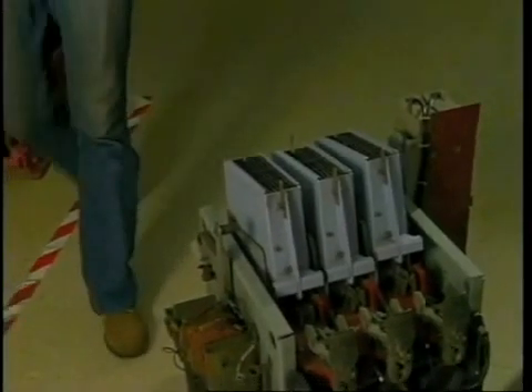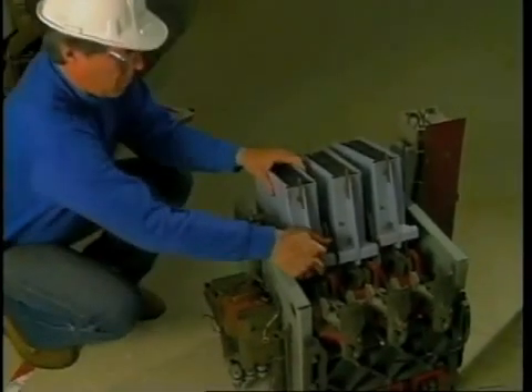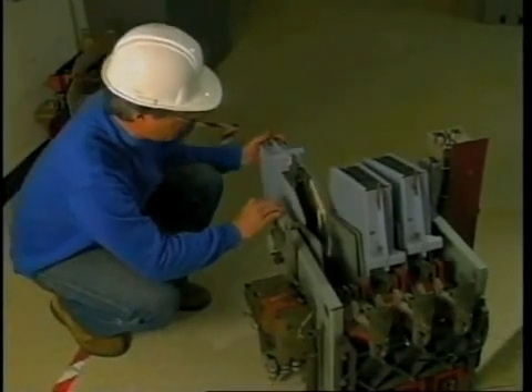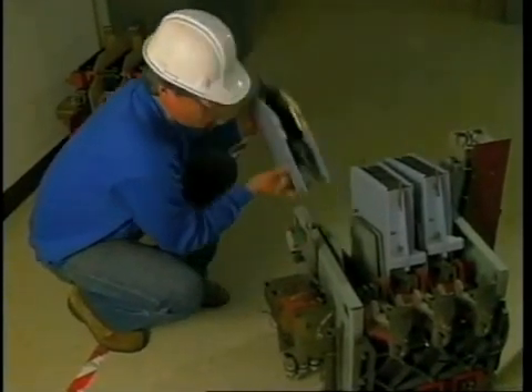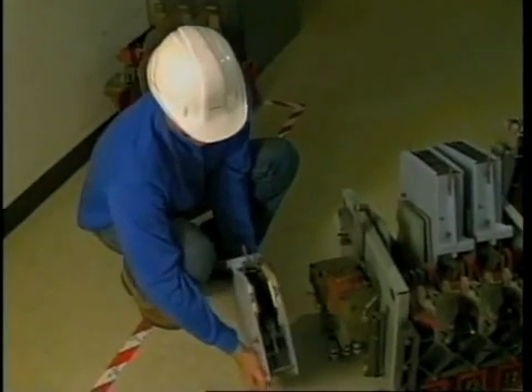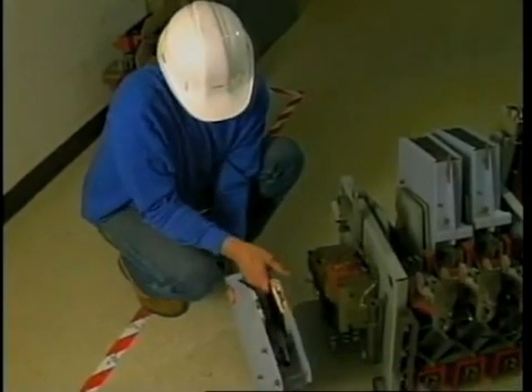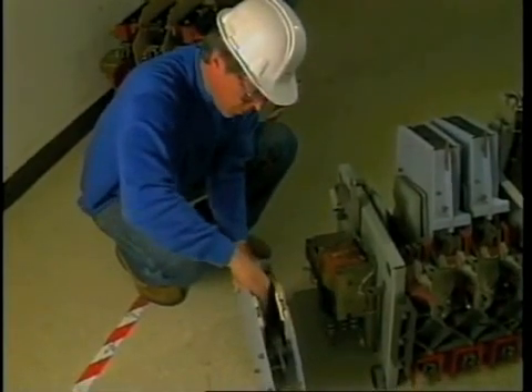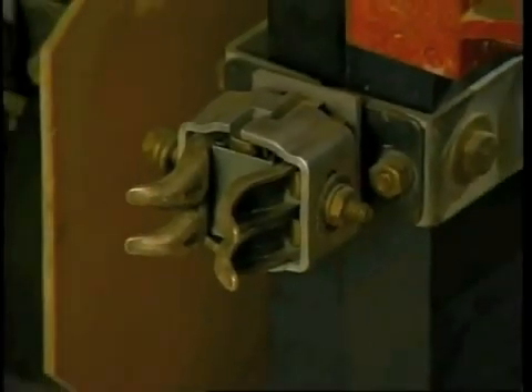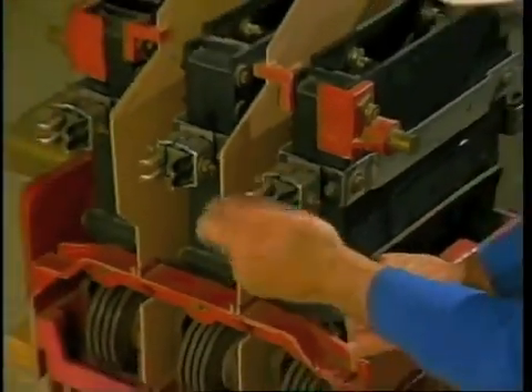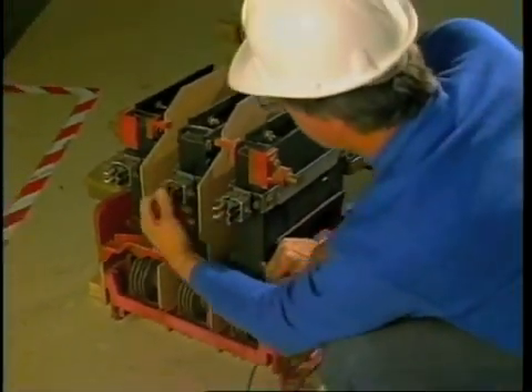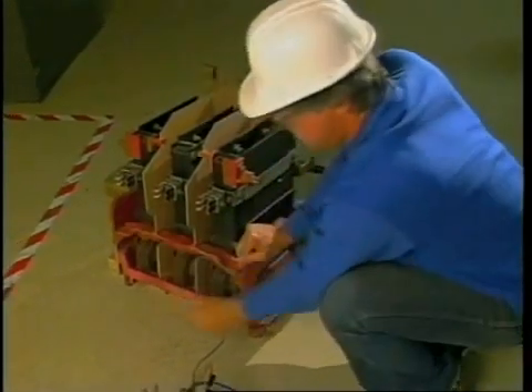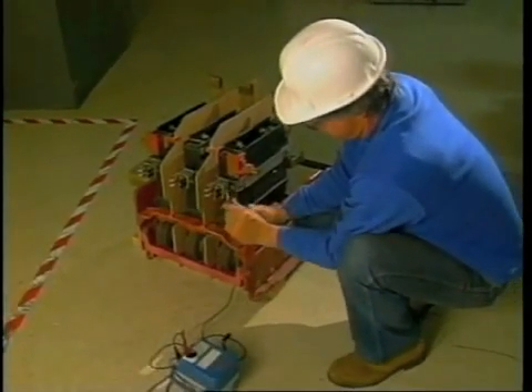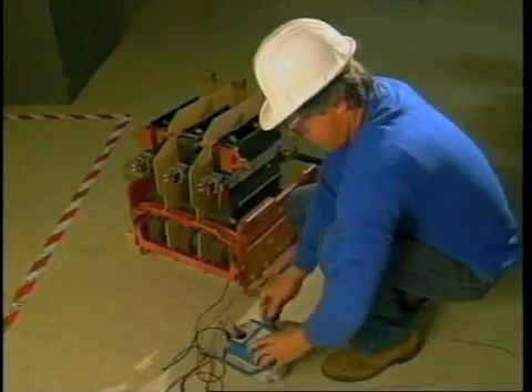All contactors have arc chutes that interrupt arcs during fault conditions. The arc chutes on contactors are smaller than those found on circuit breakers and should be visually checked following each fault condition and during routine maintenance. This should be performed while the contactor is de-energized and isolated from all control and backfeed power sources. A regular maintenance schedule must be established for contactors. The timing of maintenance depends on the frequency of operation rather than a fixed time schedule. Manufacturer specifications will indicate the need for maintenance on these devices.